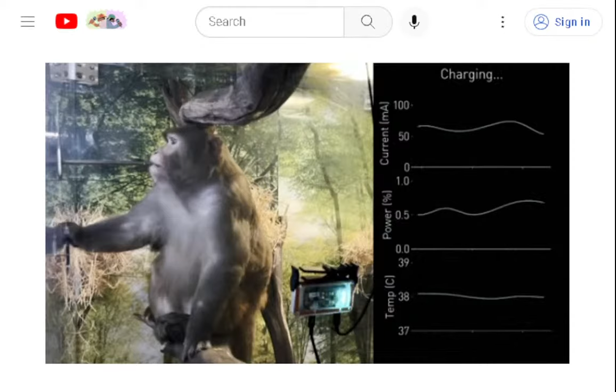I mentioned earlier that we improved the coil coupling. However, the high quality factor coils exhibit good charging performance over relatively larger distances, but as they're brought closer to the implant, what you see is a peak splitting effect, where the best, highest efficiency power transfer is pushed up into higher frequencies outside of the ISM band, required for compliance with regulated radiated emissions. In our next generation charger, we address this problem by the introduction of dynamic tuning, shown on the right. This allows us to, in real time, adjust the resonant frequency of the transmit and receive coils so that we can change their properties just ahead of degraded performance.